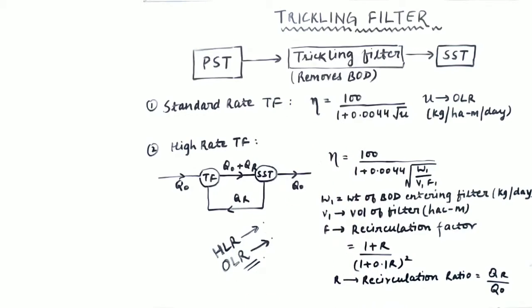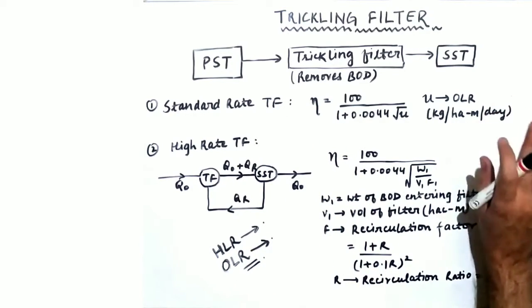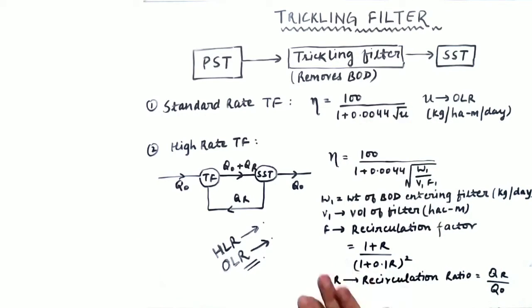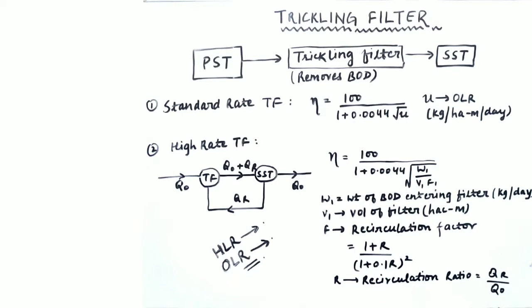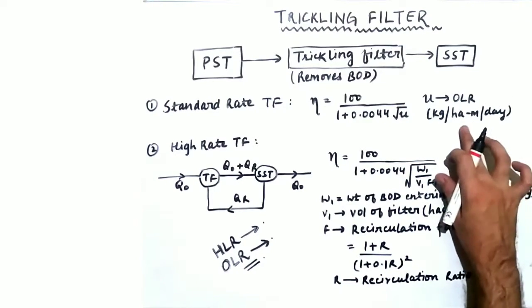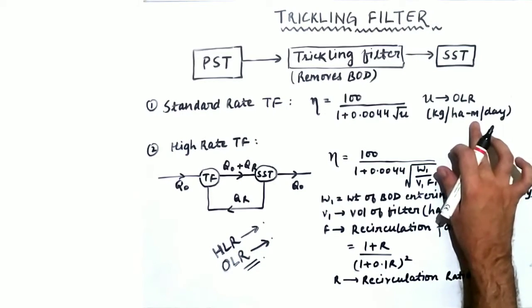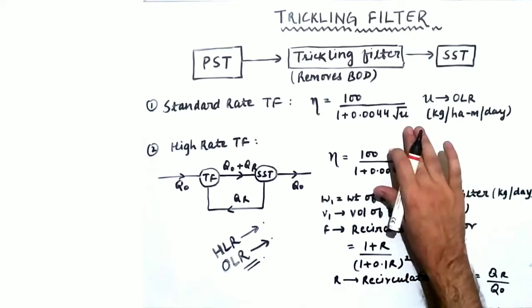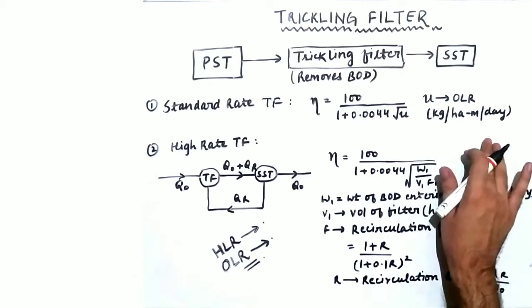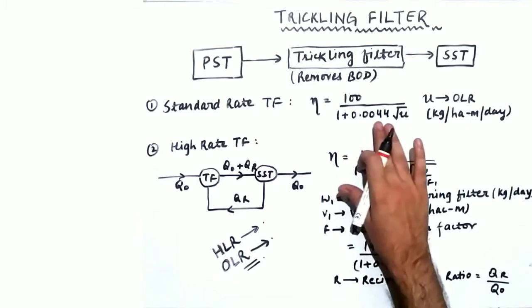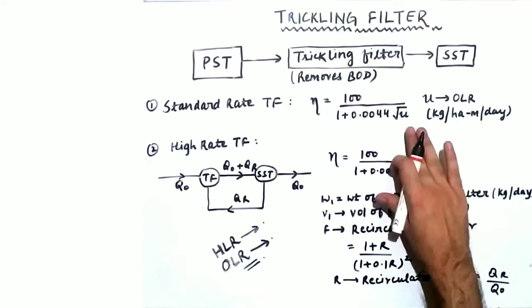The efficiency of a standard rate trickling filter can be calculated using the formula: E = 100 divided by (1 + 0.0044 × √U), where U is the organic loading rate in kilogram per hectare meter per day. If the volume is kept in meter cube instead of hectare meter, then replace 0.0044 with 0.44.